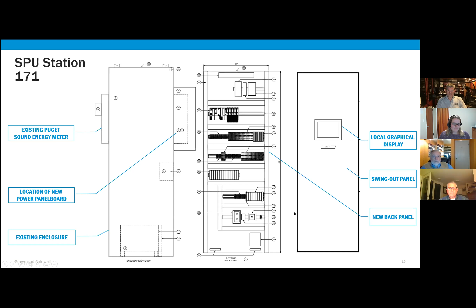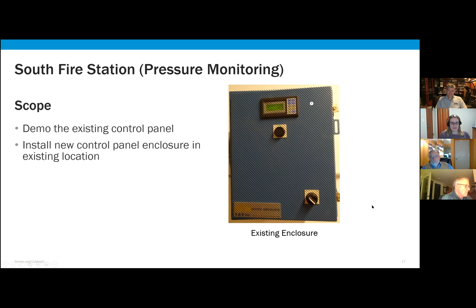All right, so at South Fire Station, the next two sites will run through our north and south fire stations. These sites currently only monitor water system pressure, and we've left space in the design for the city to add water quality monitoring here as well in the future. The plan at this site is to demo the existing control panel and then install a new control panel enclosure in this existing location. This is due to space limitations in the existing enclosure that we need to replace it at this site.